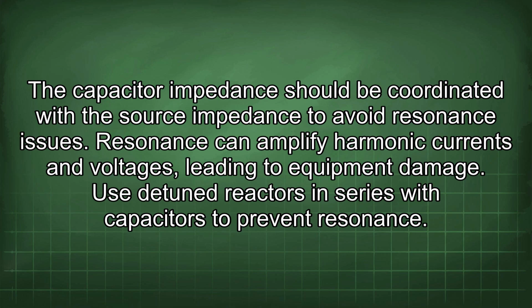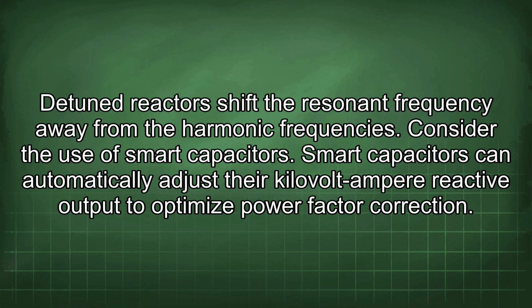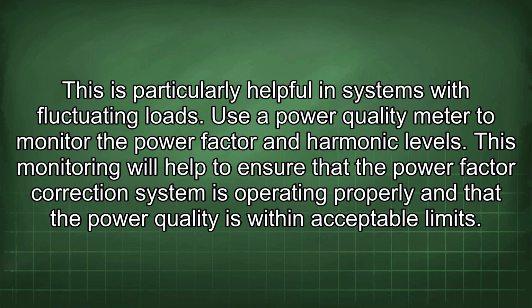The capacitor impedance should be coordinated with the source impedance to avoid resonance issues. Resonance can amplify harmonic currents and voltages, leading to equipment damage. Use detuned reactors in series with capacitors to prevent resonance. Detuned reactors shift the resonant frequency away from the harmonic frequencies. Consider the use of smart capacitors. Smart capacitors can automatically adjust their kV-ampere reactive output to optimize power factor correction. This is particularly helpful in systems with fluctuating loads.